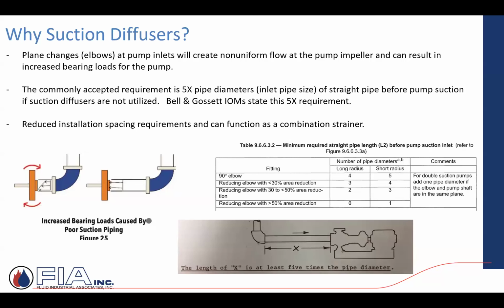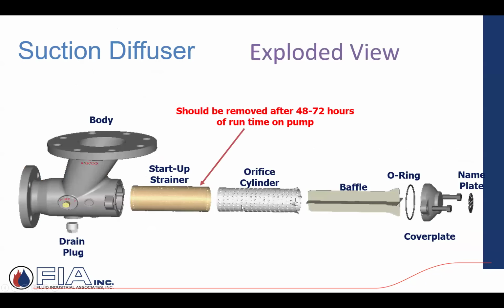So X number of years ago, some of the engineers at Bell and Gossett came up with this suction diffuser. Basically, it has a baffle or straightening vanes internally inside this body, as well as an operating strainer, which they refer to as an orifice cylinder. And then they'll also have in that suction diffuser what they call a startup strainer. That startup strainer is just there for, like they're saying here on the screen, a couple of days. Turn the system on, you commission it, you're running it.